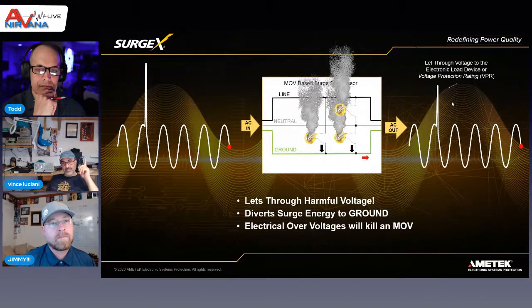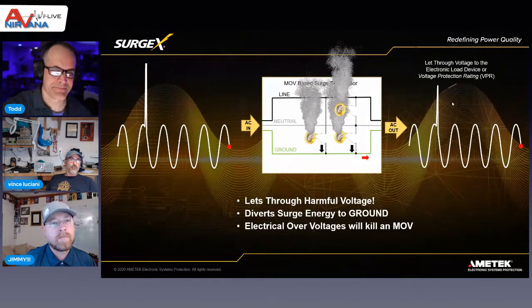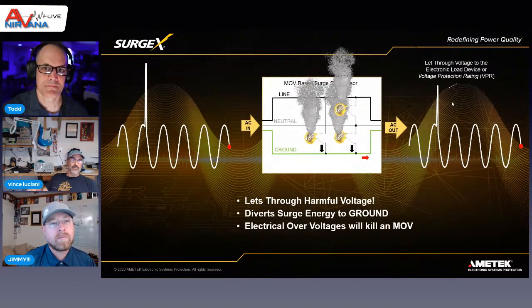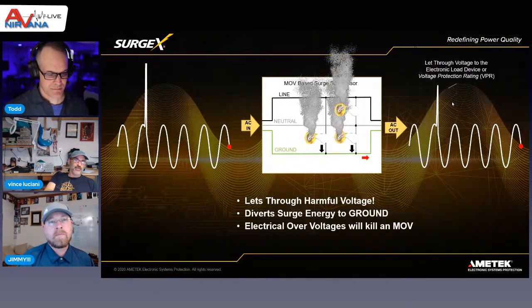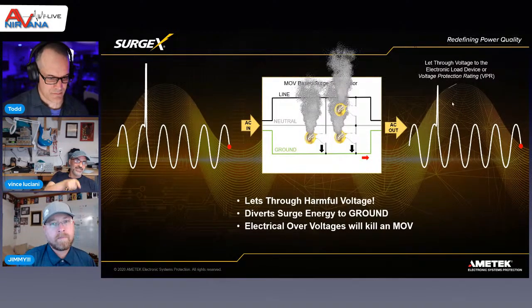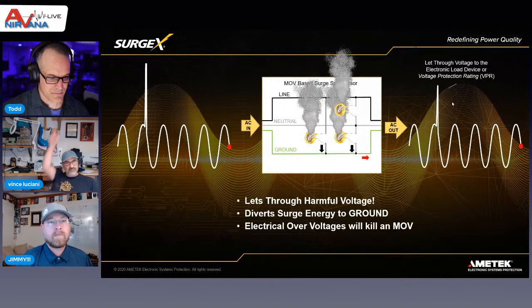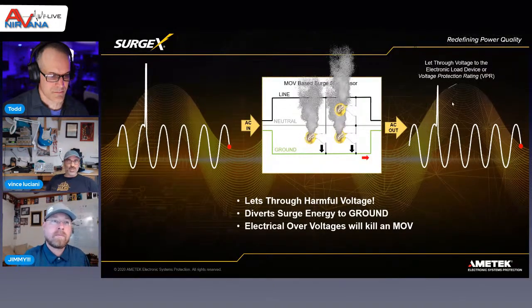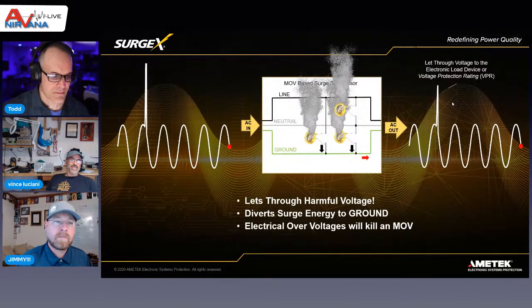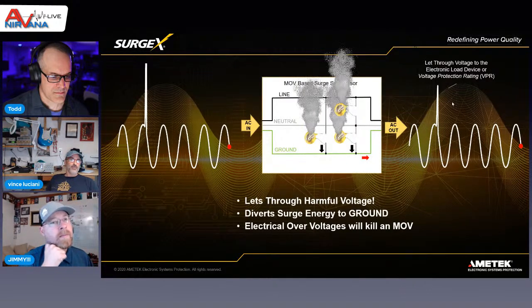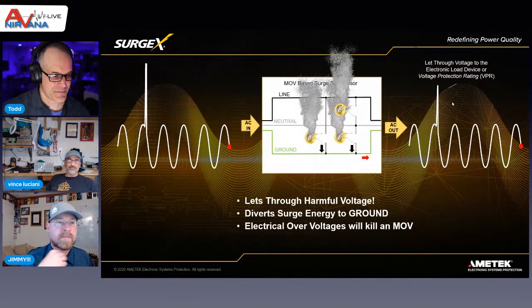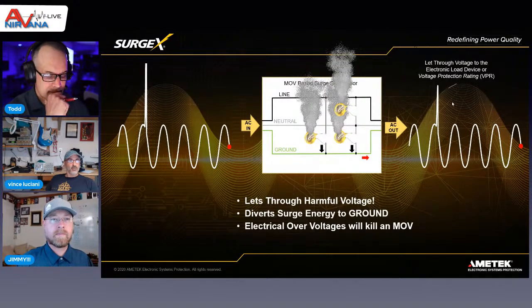The third line of defense, Jimmy mentioned it already: it's the Romex cable that's in the wall. The Romex cable can only handle a certain amount. Think of that surge we see on the screen - if you look at it from a frequency standpoint, that's an extremely high frequency signal, moving very fast up and back down, ultra high frequency. The Romex cable is not designed to support high frequency. It's like, what if you put HDMI over a Romex cable? It wouldn't go through, right? So the Romex cable not being designed to support high frequency helps you out a little bit.